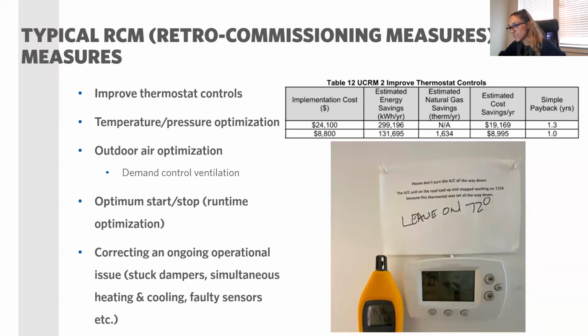But if you see in the picture, it was actually set to 65, but the unit was only able to make 70. And I was with my measurement device, and it was showing 71. So there are multiple things wrong in this picture. In general, we typically do these measurements just to see if the sensor calibrations are good, which this was within 2 degrees, so it was okay. But again, the occupants were not really complying with what the building owners or maintenance personnel were trying to achieve. If they can make sure that occupants are not overriding the set points, then in less than a year or in less than 2 years, they should be able to show the savings.